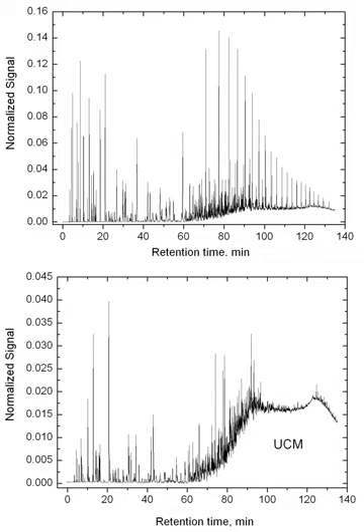A relatively recent analytical tool that has been used for the separation of UCMs is comprehensive two-dimensional GC, GC times GC. This powerful technique, introduced by Lew and Phillips, combines two GC columns with different separation mechanisms, typically a primary column that separates compounds based on volatility coupled to a second short column that separates by polarity. The two columns are connected by a modulator, a device that traps, focuses and re-injects the peaks that elute from the first column into the second column.